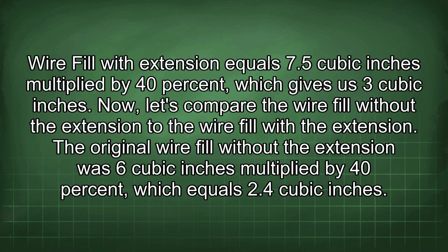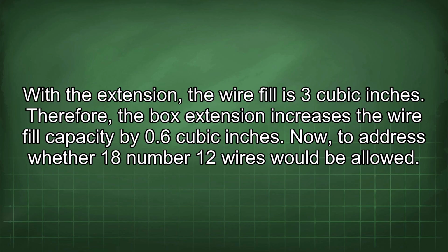Now let's compare the wire fill without the extension to the wire fill with the extension. The original wire fill without the extension was 6 cubic inches multiplied by 40%, which equals 2.4 cubic inches. With the extension, the wire fill is 3 cubic inches. Therefore, the box extension increases the wire fill capacity by 0.6 cubic inches.